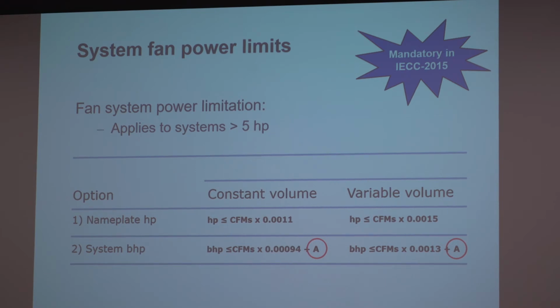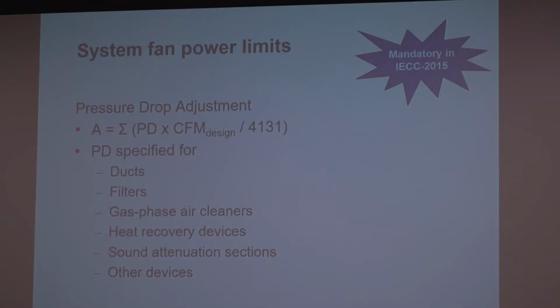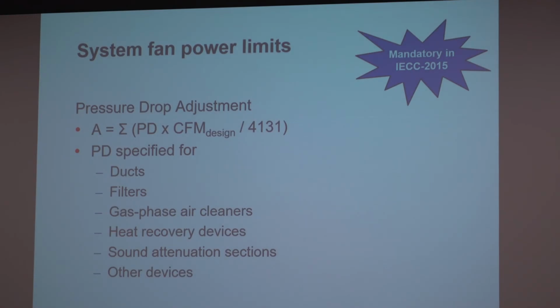So there are two paths to use here, either the nameplate horsepower of the motor or the brake horsepower of the motor. And engineers in the room, brake horsepower is essentially a calculated number that you'll get from the equipment manufacturer, or in some cases you'll have to calculate it if you're doing a built-up system, for example. But that's where that A term comes from. And there's a table that I don't have in here that's going to give you different adjustments depending on what you've got. Deeper filters, for example MERV 13 filters and better, would get a pressure drop adjustment. If you have other things in the airstream, such as energy recovery devices, you'll get some additional pressure allowances because those devices are either required for the application potentially or save energy in different ways. So that's the system fan power limitation.